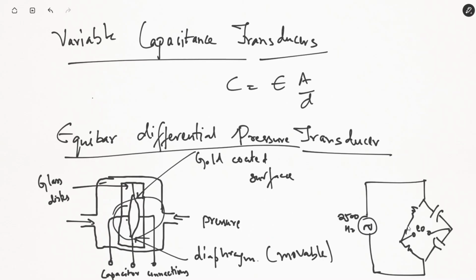You can change the capacitance of this diaphragm by applying pressure from both sides. If equal pressure is applied from both sides, the capacitance produced because of such configuration would balance this bridge and result in an output voltage that will be zero. If unequal pressure is applied from both sides, the capacitance resulting because of such configuration will make an imbalance in this bridge, and an output voltage will be produced.